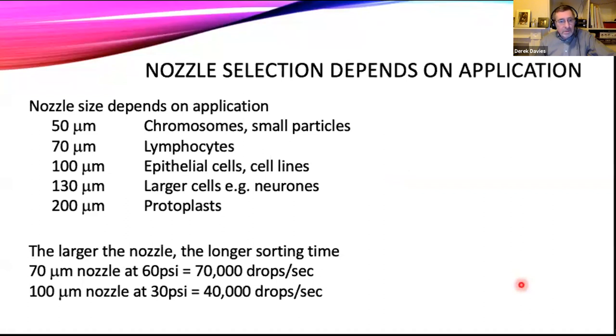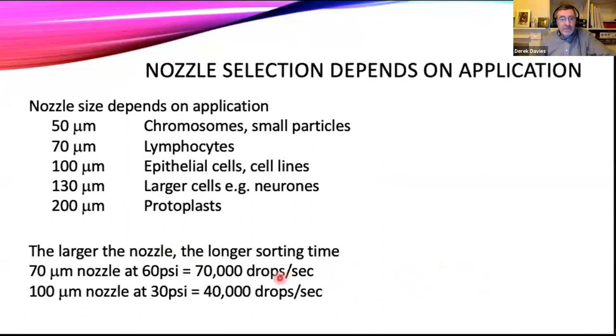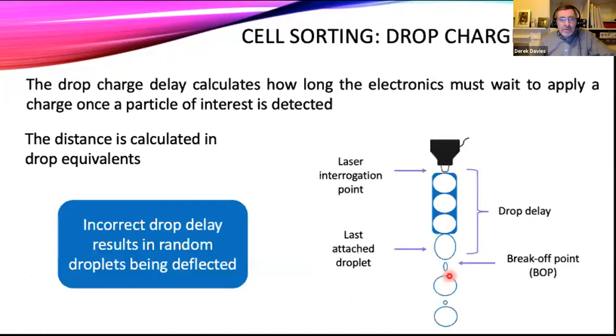If we get a blockage, if we're lucky we can be up and running again in five to ten minutes; if we're unlucky we might have to take the nozzle off, clean it by sonication, put it back on, realign the cytometer, and so on — it could take an hour. So we want to avoid clogging at all costs. The bigger the nozzle size, the longer sorting will take because we produce fewer drops. A 70-micron nozzle running at 60 psi — and that's a big difference between sorters and analyzers, which generally run at five to six psi — can make maybe 70,000 drops per second. The bigger the nozzle, the fewer drops per second.